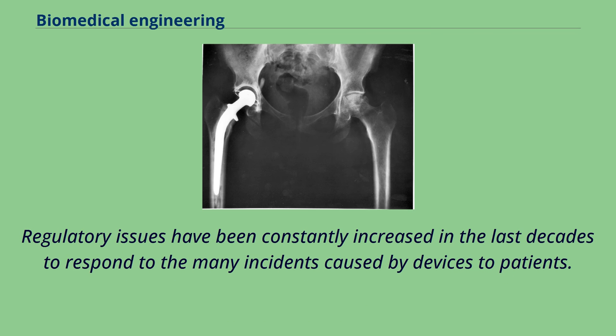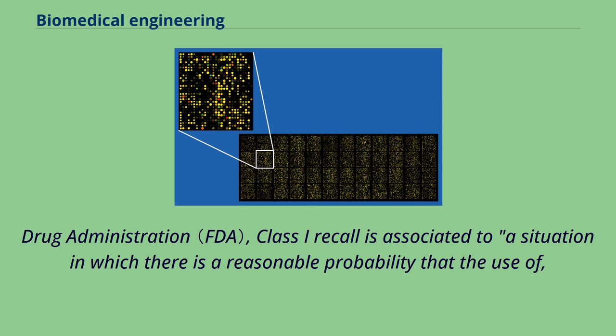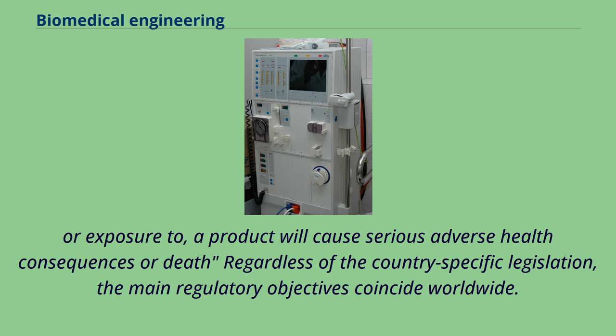Regulatory issues have been constantly increasing in the last decades to respond to the many incidents caused by devices to patients. From 2008 to 2011 in the US, there were 119 FDA recalls of medical devices classified as Class I according to the US Food and Drug Administration. A Class I recall is associated with a situation in which there is a reasonable probability that the use of, or exposure to, a product will cause serious adverse health consequences or death. Regardless of the country-specific legislation, the main regulatory objectives coincide worldwide.